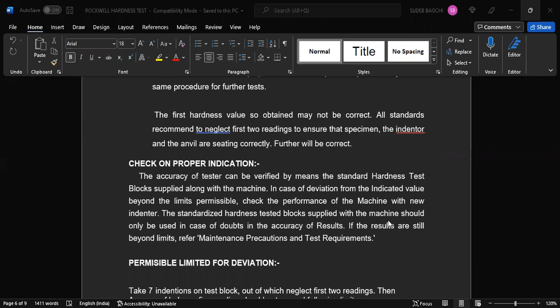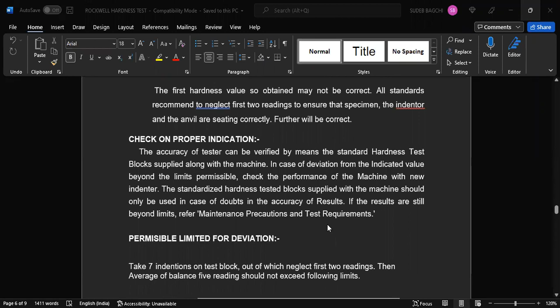Supplied along with the machine, in case of deviation from the indicated value beyond the permissible limit, check the performance of the machine with a new indenter. The indenter and the standard hardness test block supplied with this machine should be used only in case of doubts in the accuracy of the result. If the results are still beyond limits, refer to the maintenance procedure.